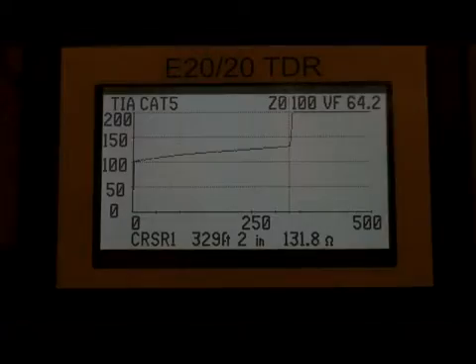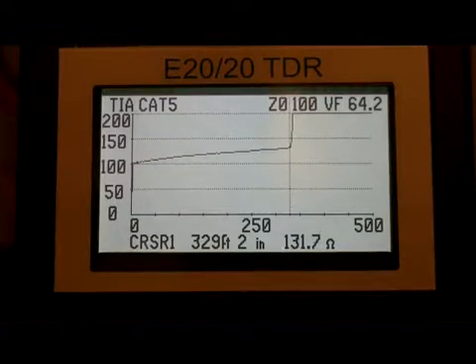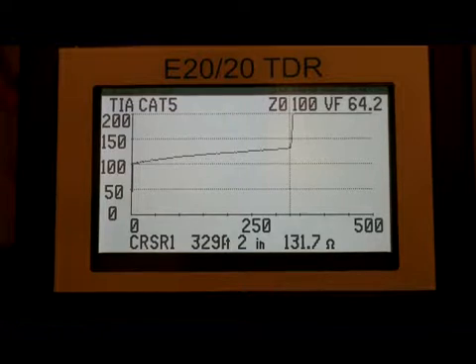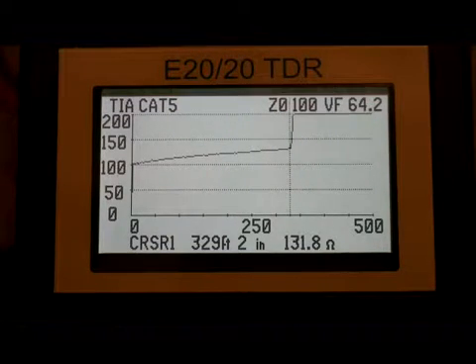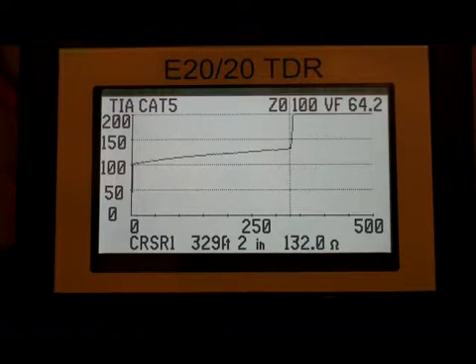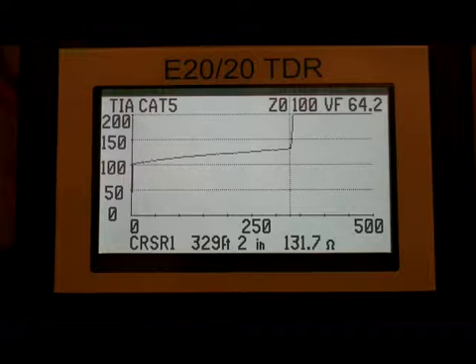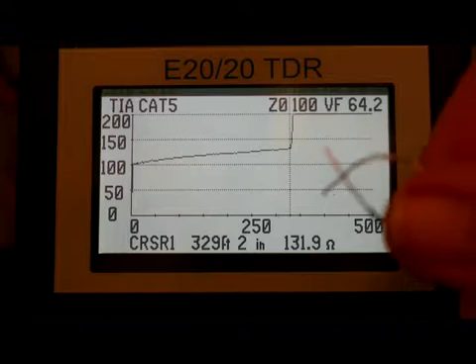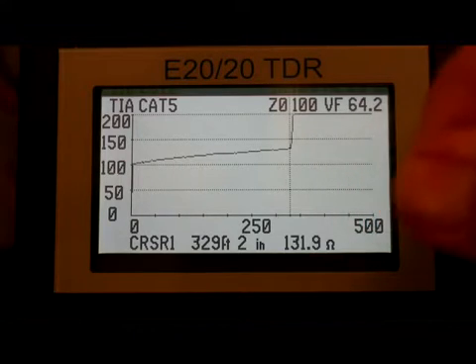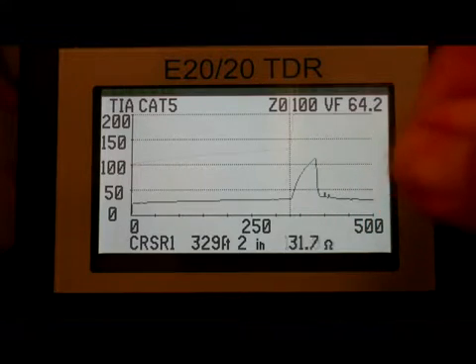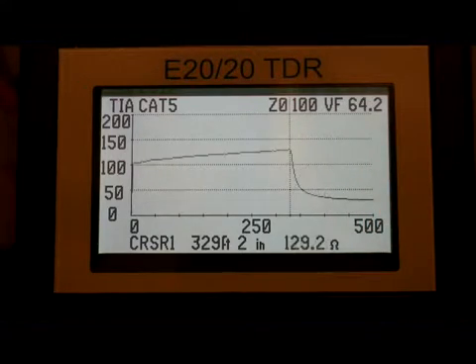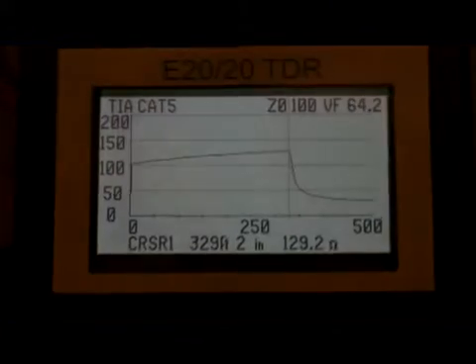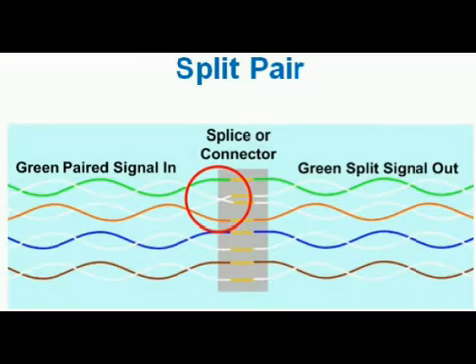Our first cable is 100 meters, or 328 feet, as shown by cursor 1, and appears normal. The loop resistance represented by the trace's dribble-up is obtained by measuring the delta between the cursors positioned at the start and end of the cable. The end is open right now, as shown by the straight upward trace at the far end. If I short pair 1 at the far end, you'll see the trace go towards 0 ohms.